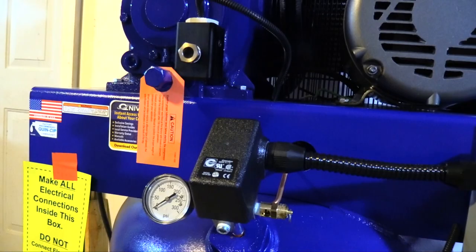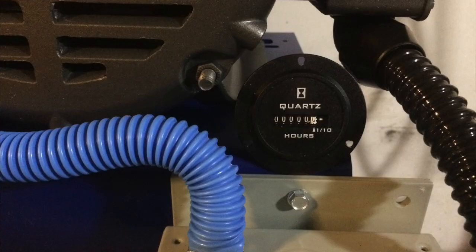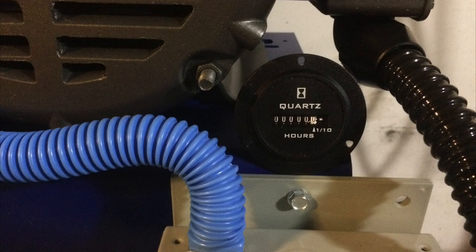The break in period for the Quincy air compressor is 50 hours. At the 50 hour interval, the oil must be changed. Each subsequent 200 hour period also requires an oil change to meet the Quincy warranty requirements. To keep track of the hours, I bought a TruMeter hour meter to install on the air compressor.